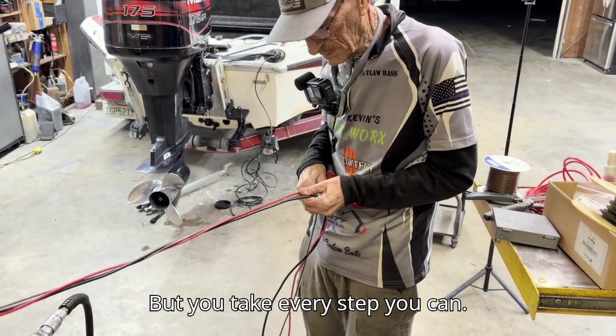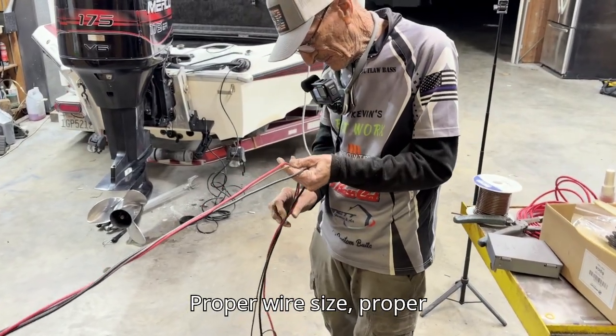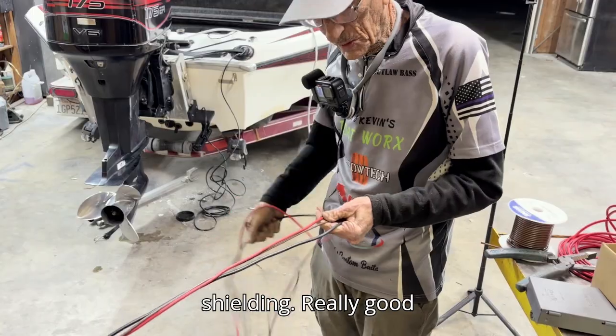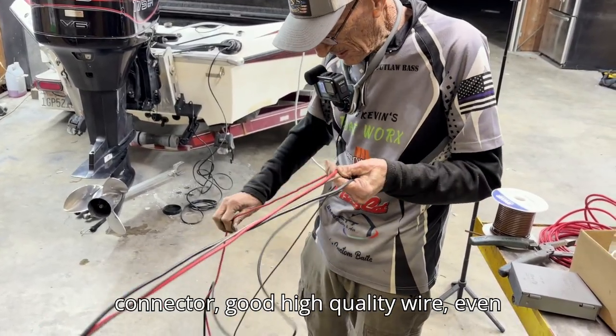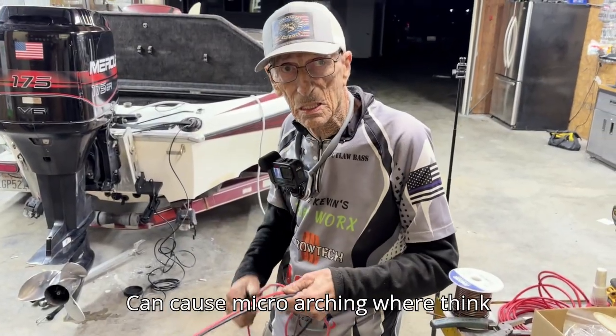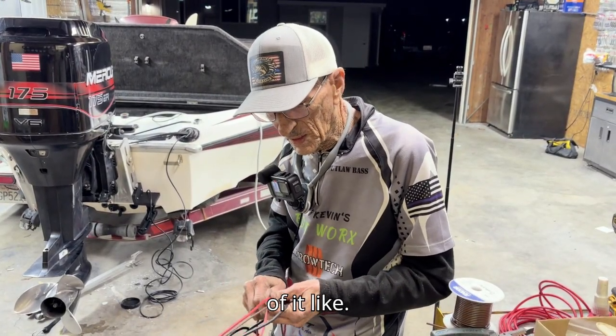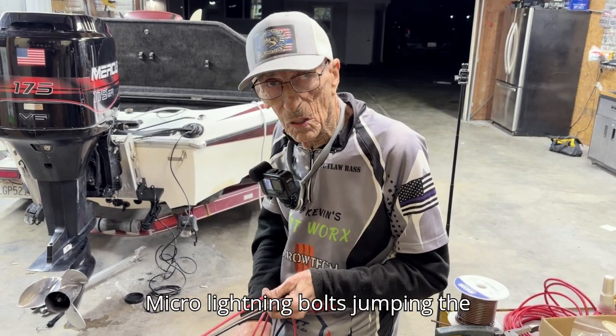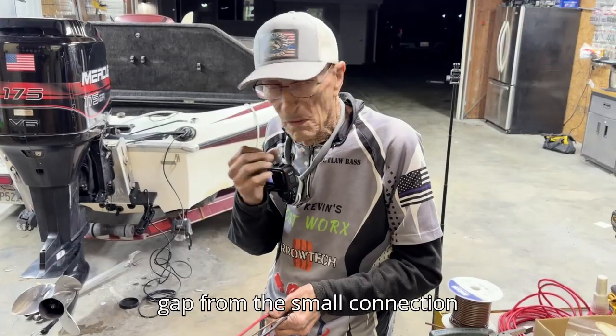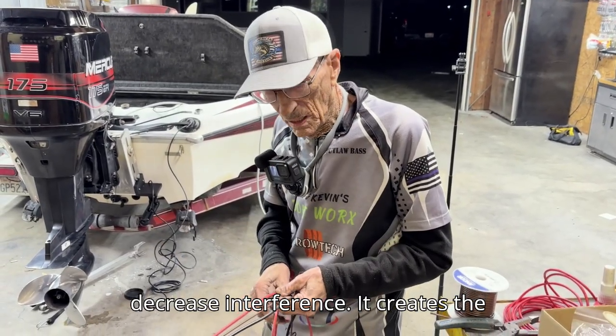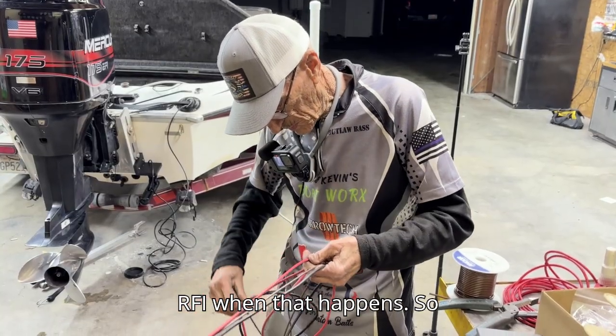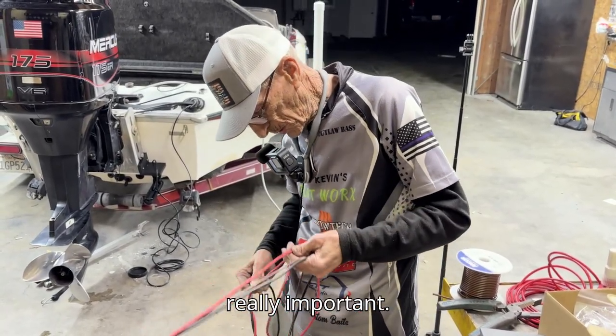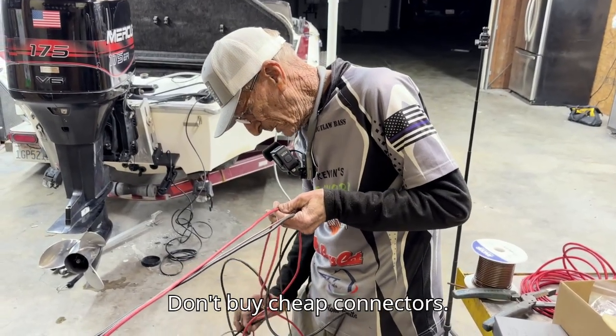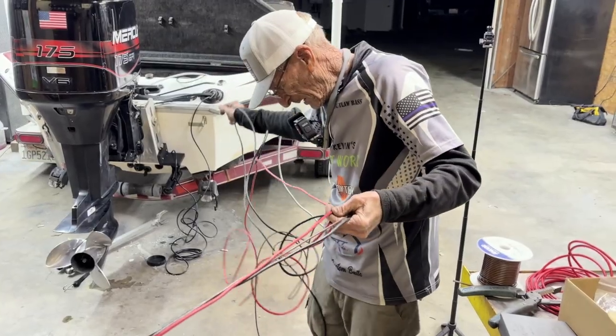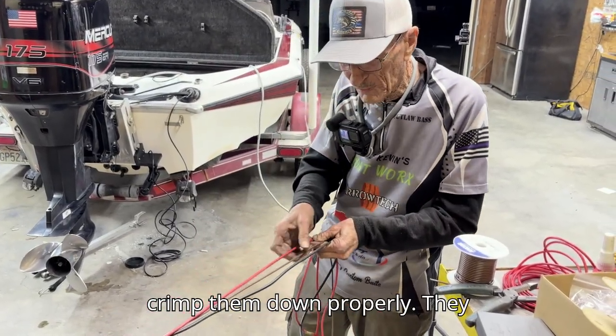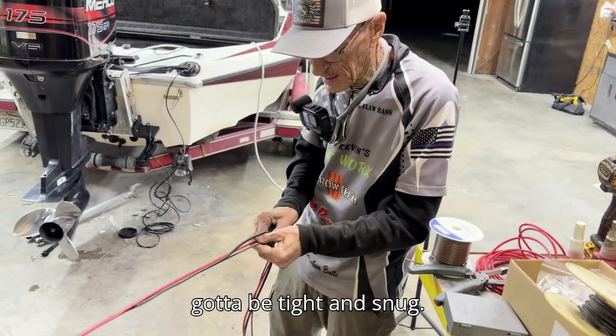But you take every step you can. Proper wire size, proper shielding, really good connectors, good high quality wire. Even a poor connector, if it's not tight, can cause micro arcing, where think of it like micro lightning bolts jumping in the gap of the small connection. That creates interference, it creates the RFI when that happens. So connection quality is really, really important. Don't buy cheap connectors. Get really good crimping tools to crimp them down properly. They've got to be tight and snug.